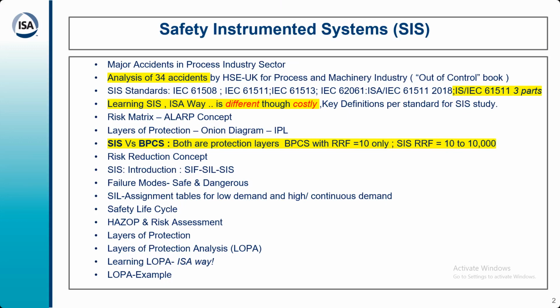One of the key points which I wanted to focus on was SIS versus BPCS, which is a process control system, rather basic process control system. Now, both are protection layers, but the major difference is your BPCS cannot be allotted risk reduction more than a factor of 10, whereas SIS risk reduction factor ranges from 10 to 10,000. You can see the difference between the two.